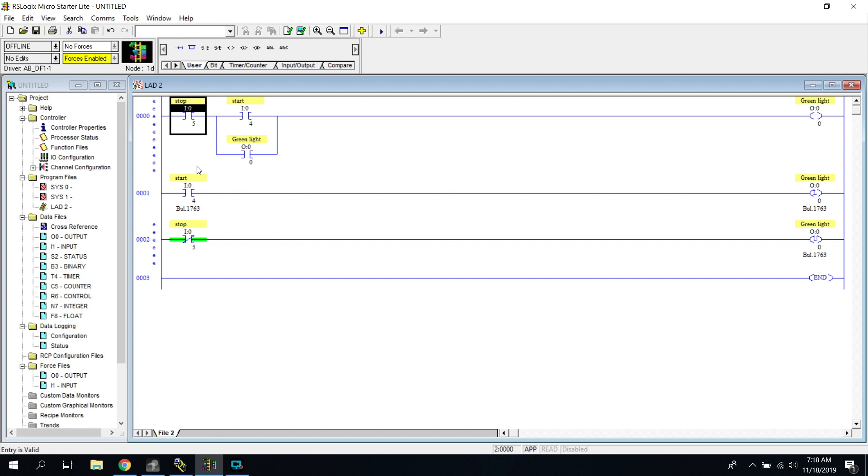Well, that green light or that crusher is going to continue moving. It's not going to stop because it never received a signal to unlatch. Well, if that happens to this one right here, this conditional one, it actually will turn itself off because it no longer has power coming from that stop button.